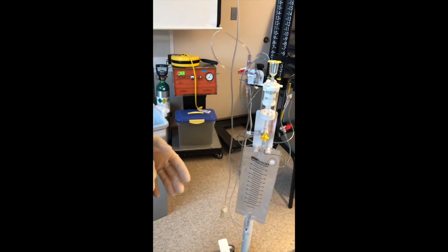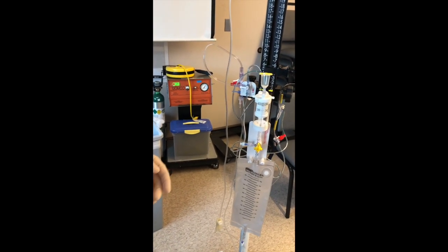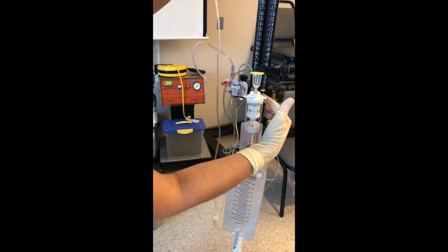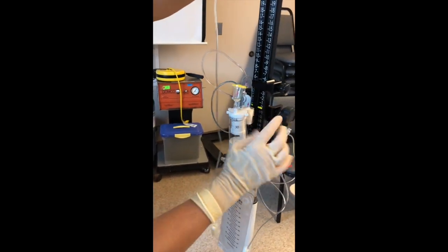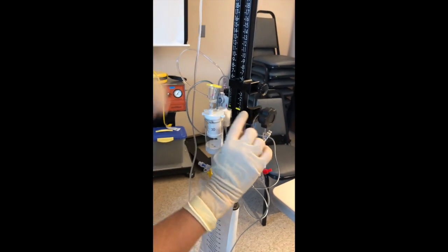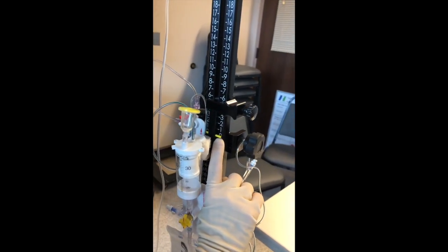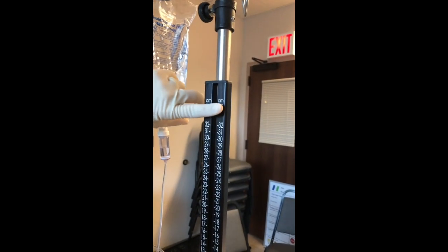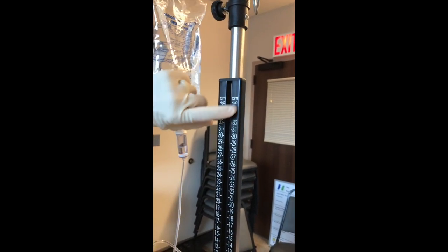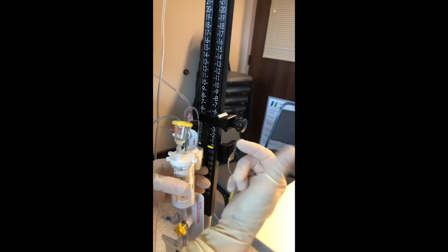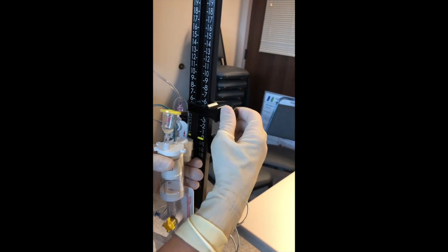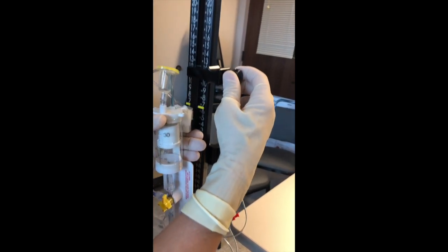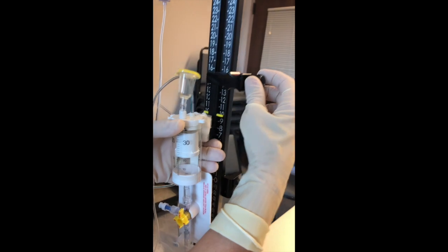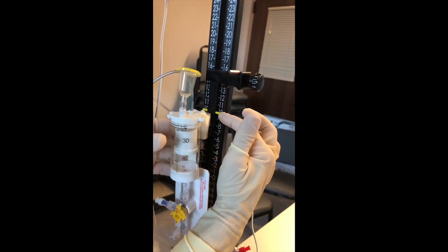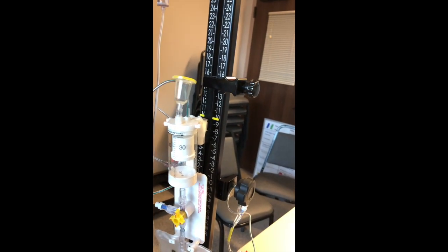You will then adjust the prescribed level in centimeters of water and secure in place with the securement knob. So here is your level, and this is at 0. You want to make sure that you're using a ruler that has centimeters of water. If there are two different, always go with the centimeter of water. Here's your 0. And if the physician prescribes that he wants it at a different level above the tragus, you could just simply slide it up and secure it at, for example, 10 centimeters of water above the tragus.